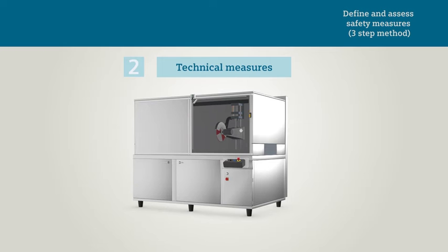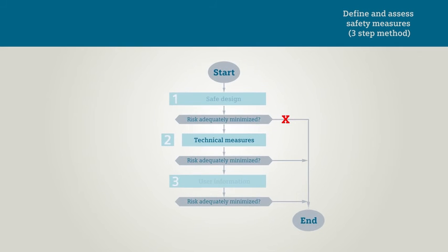To be able to assess the current safety of the machine, you must evaluate your safety measures. The risks are to be reduced to an acceptable extent using additional technical protective measures until no further technical measures are required. In the example, the additional technical measures provide sufficient safety to achieve an acceptable residual risk. Therefore, you do not have to take any further measures. If further unacceptable risks were to remain after you had taken the measures, an iterative process would have to be performed until the risks had reached an acceptable level.